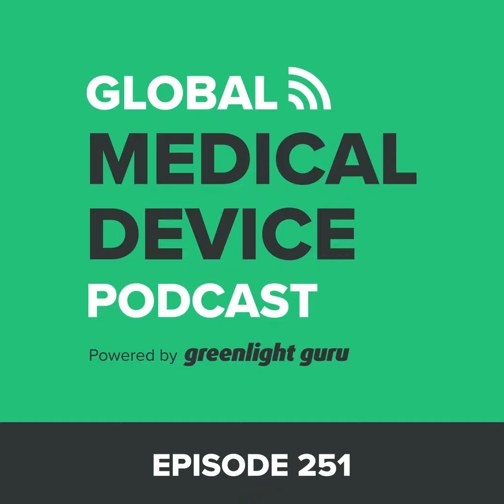That's what I was going to start with too. So good. Dive in. The quality system requirements, both in ISO and FDA, they've added design controls, which is great because it's sort of the front end. So as you look at design controls, there are design inputs, design outputs, design verification, design validation. Design output, that is what is your design going to be? And so that's the design output. Now, everything that's developed out of design controls is part of what's called the design history file. So your design history file is everything associated with design.